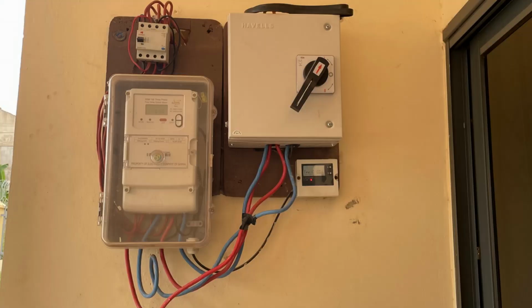So the first thing that I saw when I went there was they've got a 16mm cable coming in from ECG. Okay, that's genuine. That's okay. That can take about 80 amps, so that's fine. That comes into the 100 amp breaker supplied by ECG, which then goes into the meter, and then from the meter they have a changeover. The idea of that changeover is so that they can have a backup generation that can support the house, as well as when ECG is not available.